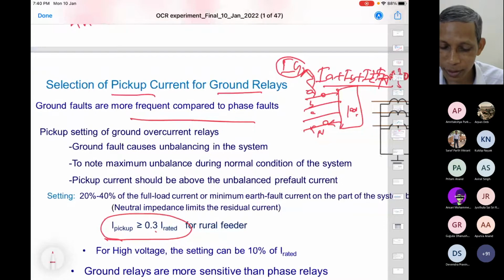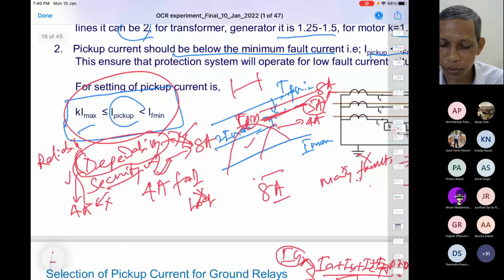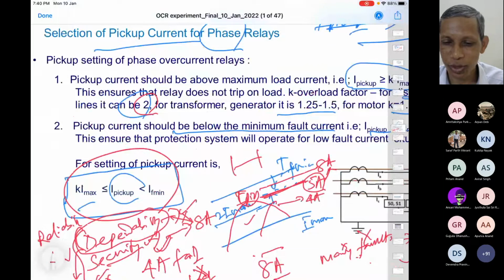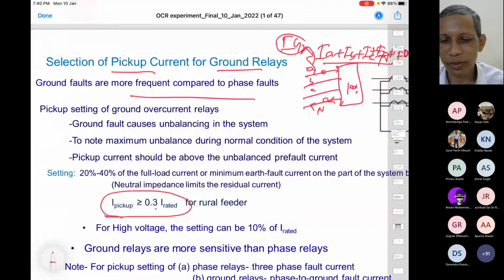Whereas in the earlier case, in case of phase, we made it twice the full load current for a distribution system. Here you are talking about 30% of the full load current, 20% of the full load current, and maybe even less you can do if the corresponding system is very good. For high voltage, the setting can be 10% also.